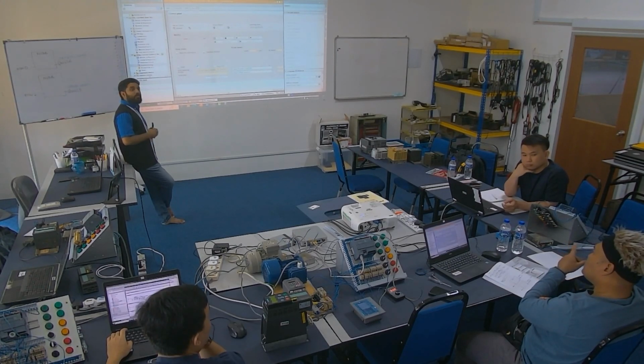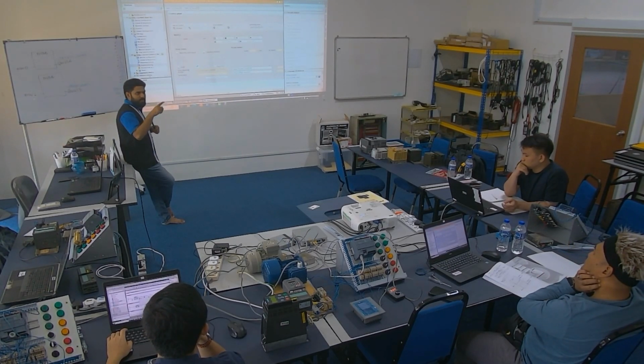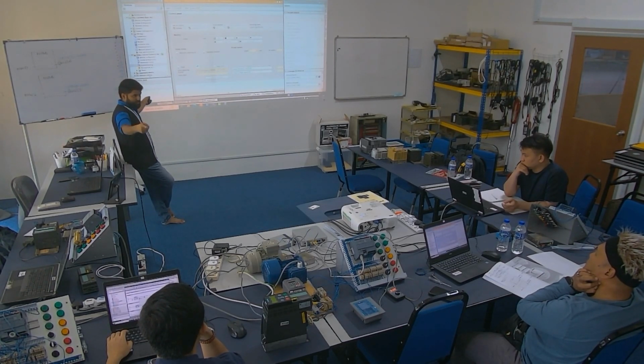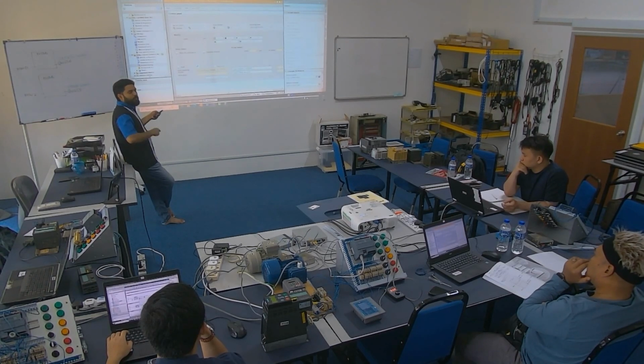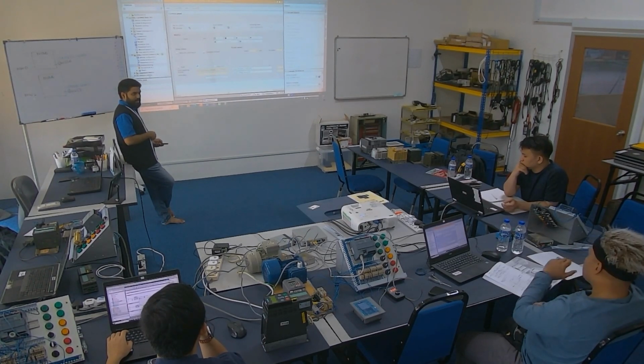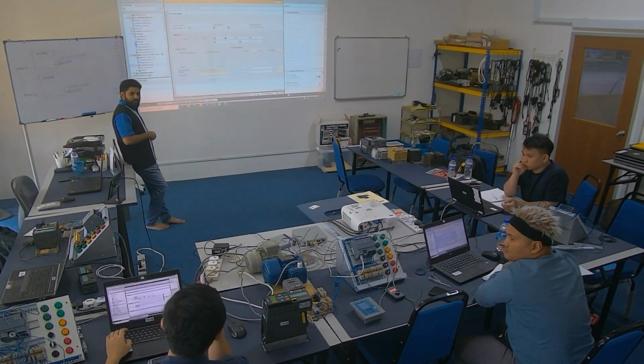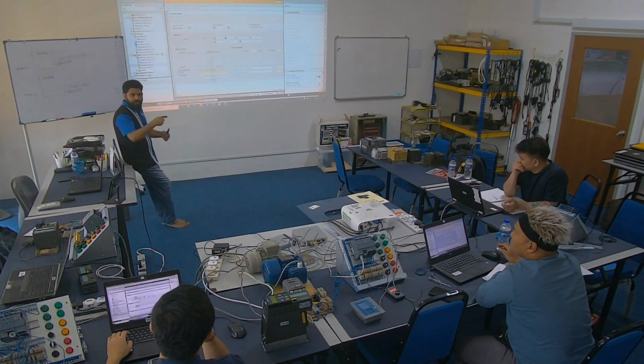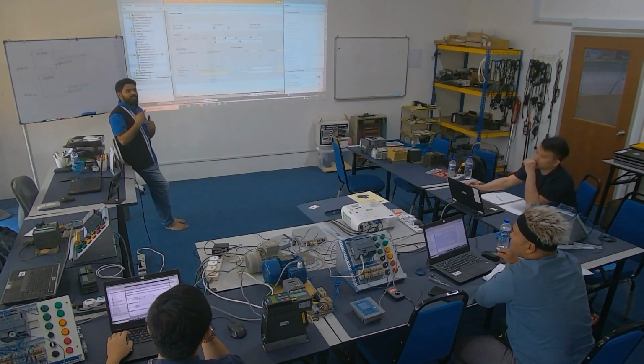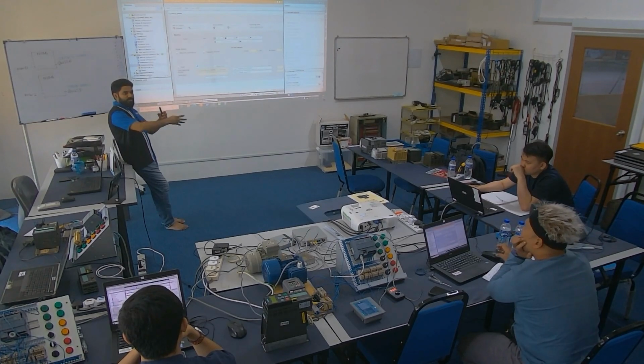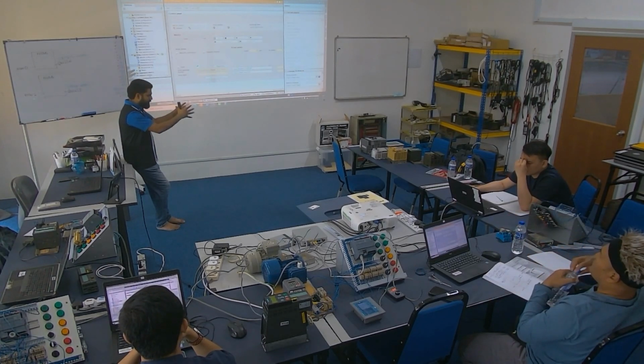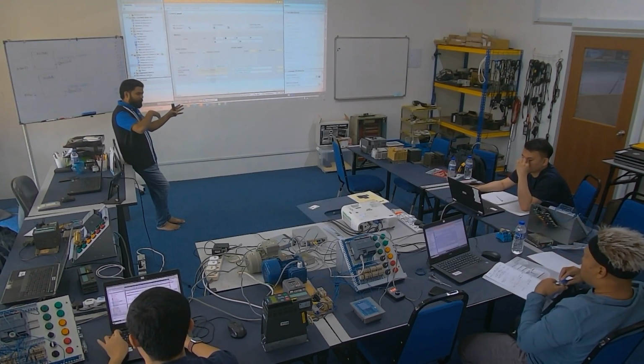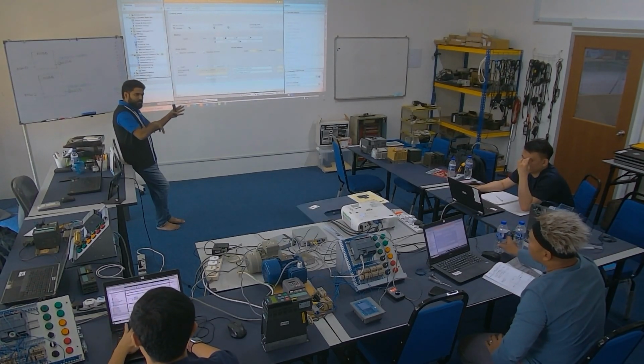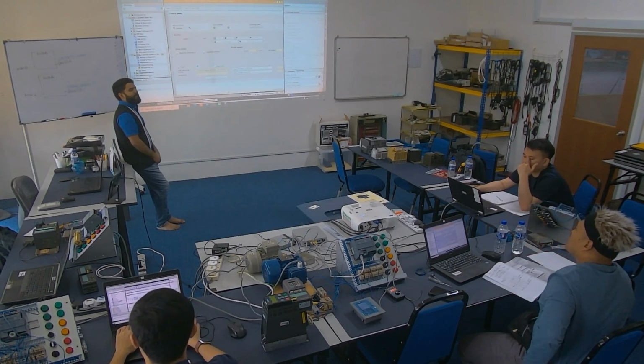If you want to, because you also do the commissioning, correct. If you download your VFD settings to the drive, then you need to do this before testing your program. Why must you do this? Because you downloaded the settings, it's like a new setting already, so you need to do commissioning. You already did the commissioning, already tested, so the drive is ready to run. But if you download a new configuration again, the drive needs to do the commissioning before it's ready to run. Understand? Okay, good.